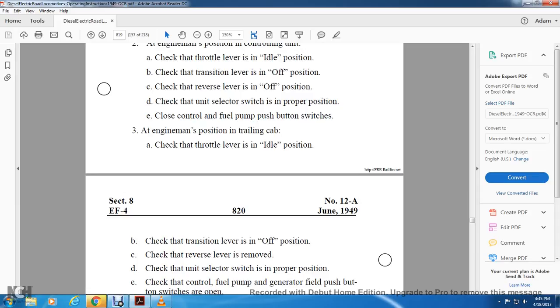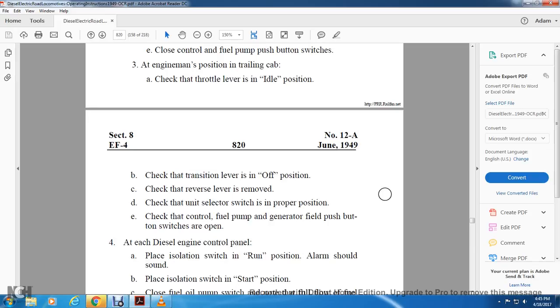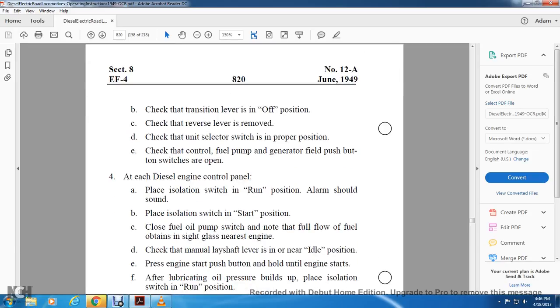Check the control, fuel pump, generator field push button switches are open at each diesel engine control panel. Place the isolation switch in the run position. Alarm should sound. Place the isolation switch in the start position. Close the fuel oil pump switch and note that full flow of fuel is obtained at the sight glass nearest the engine. Check that the manual layshaft lever is in or near idle position.